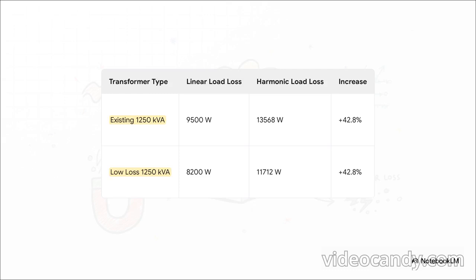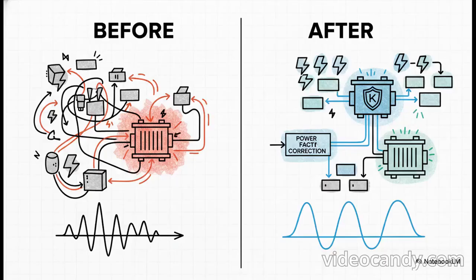Take a standard transformer. When you switch its workload from simple linear loads to modern harmonic loads, the energy loss jumps by almost 43%. And look at this, even if you start with a more efficient low-loss model, you still get hit with that exact same 43% penalty. It just proves that being generally efficient isn't enough. You need equipment specifically designed for the kind of dirty power our world actually uses today.